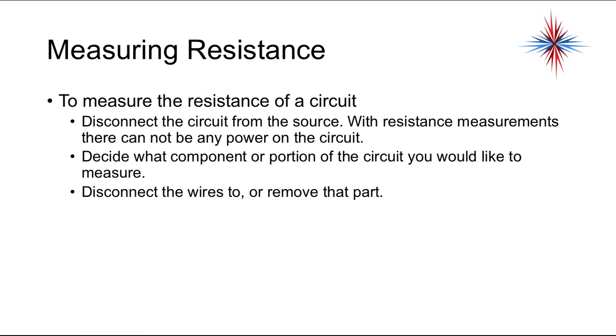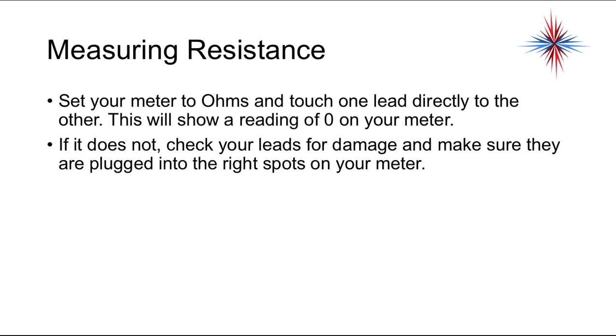Now, resistance is a little bit different than the others. Okay, to measure resistance, you have to disconnect the circuit from a source. With resistance measurements, there cannot be any power on that circuit. Decide what component or portion of the circuit you would like to measure. You have to disconnect wires to or remove that part. For resistance, we want to isolate any components. Set your meter to ohms and touch one lead directly to the other. We want to verify our meter's good to start with. Okay, that will show a reading of 0 on your meter. If it does not, check your leads for damage and make sure they're plugged into the right spots on your meter.